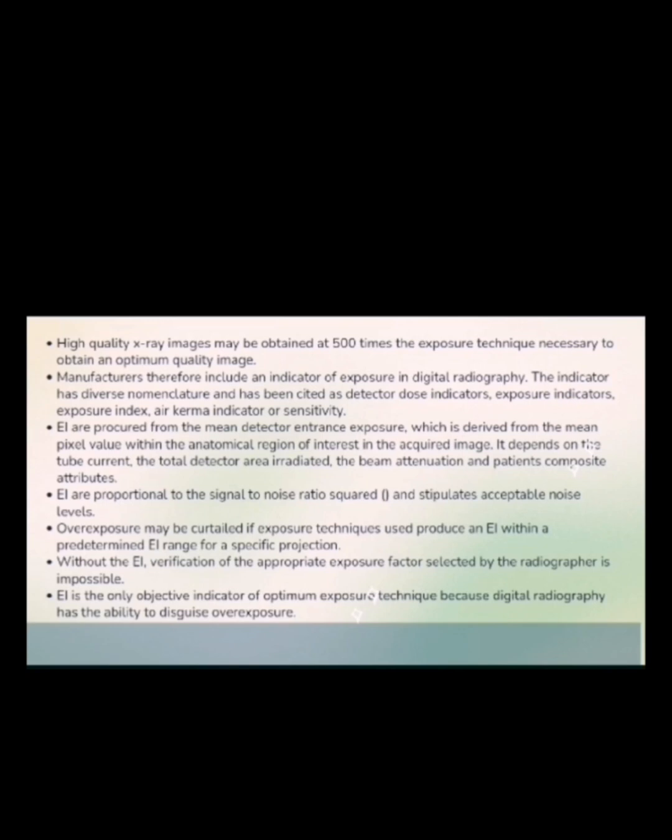On to the next bullet. While the wide dynamic exposure latitude is indicated in literature as an advantage of digital radiography, there has also been evidence of its augmentation of exposure creep. That's why manufacturers included an indicator of exposure in digital radiography. This indicator has diverse nomenclature and has been cited as detector dose indicator, exposure indicator, exposure index, air kerma indicator, or sensitivity. Hereafter, the term exposure indicator will be used.